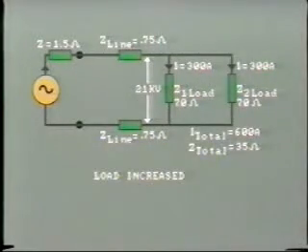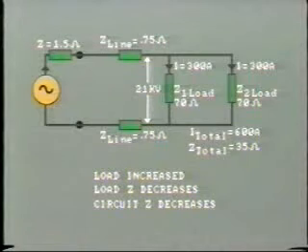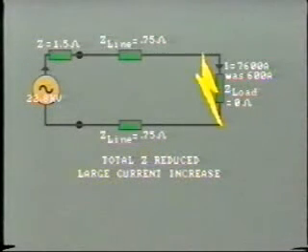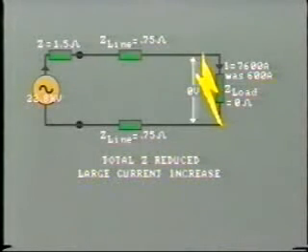We know in practice that it is all a lot more complicated than this — we have three phases to worry about and moreover, the impedances may be at different angles and therefore would have to be added vectorially. But the conclusions are very clear. First, an increase in load decreases the load impedance and therefore decreases the total circuit impedance. Secondly, as a result of the short circuit, the total impedance is greatly reduced and the consequent increase in current is dramatic — in our example it has increased by approximately 13 times. Thirdly, the voltage at the short circuit has decreased to zero, and as a result the voltage all along the line is also reduced.